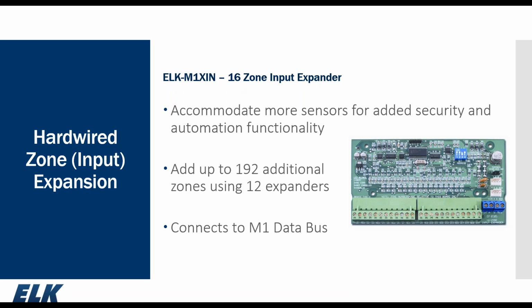The dip switches on the board, the blue dip switches here, set the address. That address will determine the starting zone number. For instance, address 2 would be zone 17 through 32. Address 3 would be 33 through 48 and so forth.